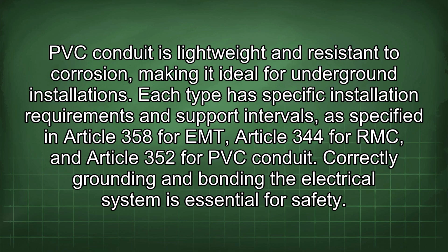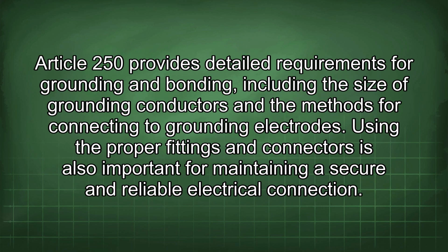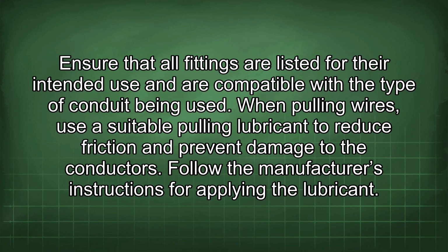Correctly grounding and bonding the electrical system is essential for safety. Article 250 provides detailed requirements for grounding and bonding, including the size of grounding conductors and the methods for connecting to grounding electrodes. Using the proper fittings and connectors is also important for maintaining a secure and reliable electrical connection. Ensure that all fittings are listed for their intended use and are compatible with the type of conduit being used.